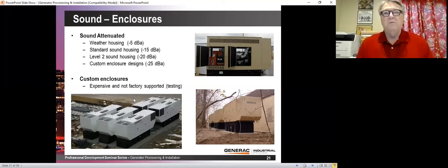A weather housing will typically reduce the sound about 5 dBA. A standard sound attenuated housing, which we now call level 1, they used to just be called a sound housing. Now it's level 1, about 15 dBA, level 2, 20 dBA, or you can go to a level 3, which is starting to get some acceptance, or you can actually build custom enclosures.